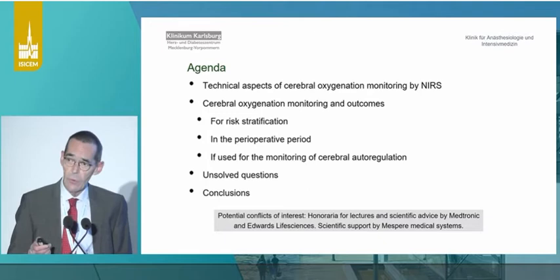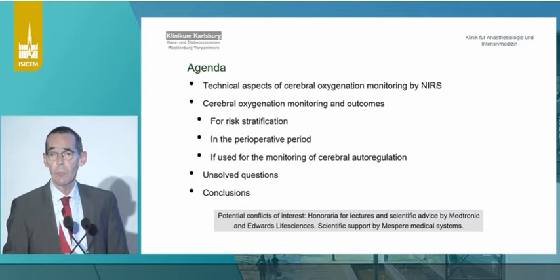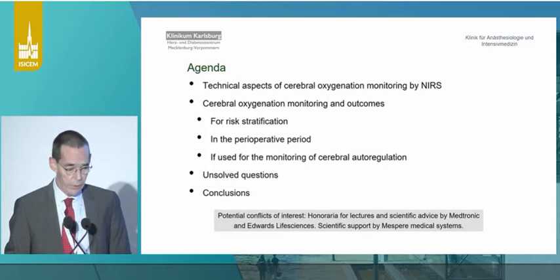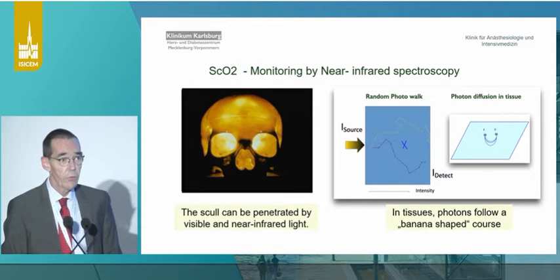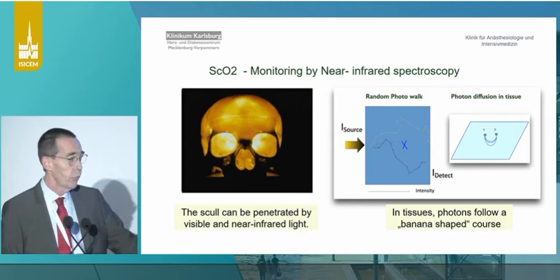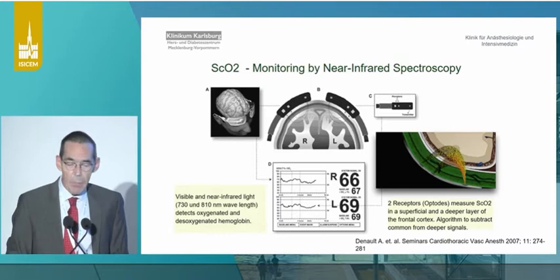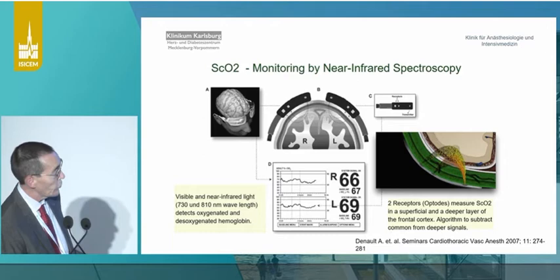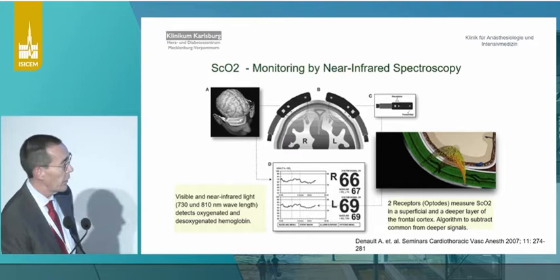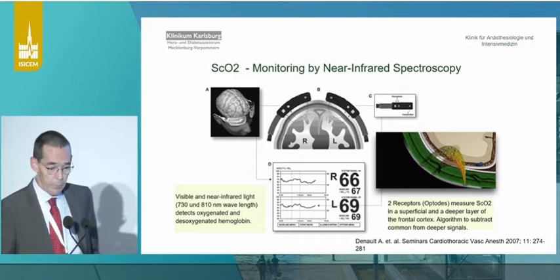It's not that simple, as already brought up in the first talk. I'd like to start with some technical aspects and then present how we can use this technology, and discuss the unsolved questions. We can use it because the skull can be penetrated by light, and photons follow a banana-shaped path within tissues. If you enter some light by light-emitting diode and use two sensors a little bit apart from each other, you can get information about the oxygenation state in the more superficial or the deeper parts of the brain. By subtracting one piece of information from the other, you get information about tissue oxygenation in the vessels in that specific area.